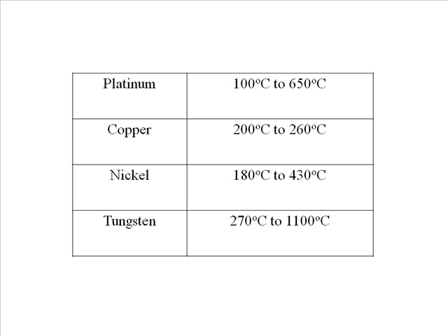If it is copper RTD then it can measure temperature accurately from minus 200 to 260 degrees centigrade. For nickel this range is from minus 180 to 430 degrees centigrade.